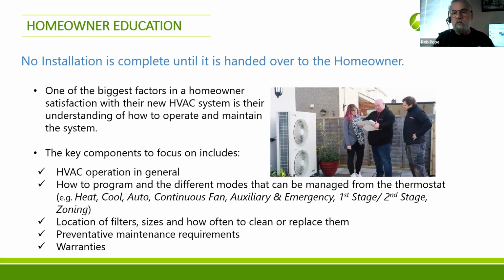Let them do a walkthrough, let them understand the system, and make sure all that documentation is in front of them and they know what it is, what it means, and what to refer to. If they're having a performance issue, something's going wrong, it's not heating up in wintertime, they know who to call, and that technician can look at the record and see what the condition was when it was commissioned.